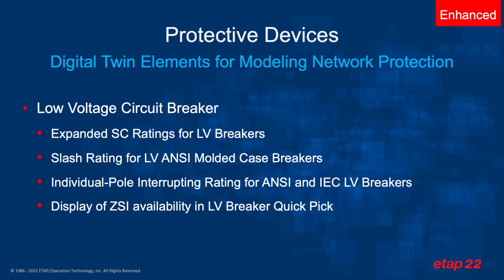We've not only expanded the short circuit ratings for the low voltage breakers, but we've done so by adding the slash rating for LV ANSI molded case breakers and individual pole interrupting rating for ANSI and IEC low voltage breakers. We're also showing ZSI availability in the LV breaker quick pick, allowing you to identify whether a particular circuit breaker is capable of zone selective interlock or not.